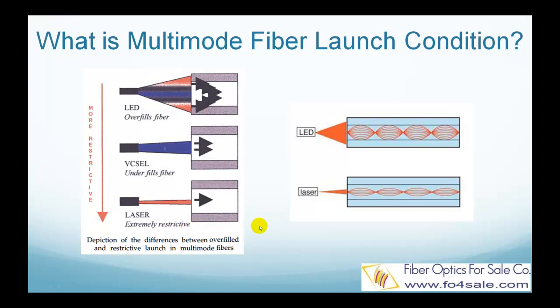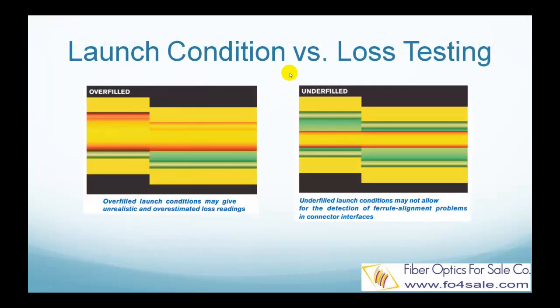So why do launch conditions matter? What is the impact on multi-mode fiber loss testing? These two pictures show what happens when two fiber connectors are misaligned. The red beams represent the modes in the fiber, the green parts represent the fibers, and the yellow parts represent two separate connectors that are mated to each other. In the overfilled condition, the light beam occupies the whole fiber core. Since there is a lateral misalignment, part of the higher order modes are blocked and lost.